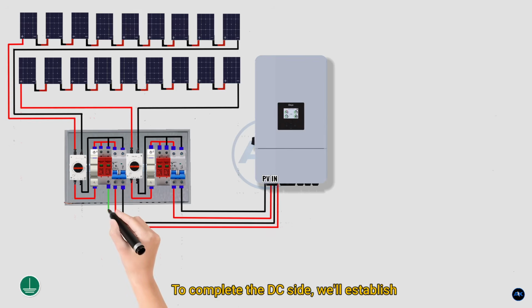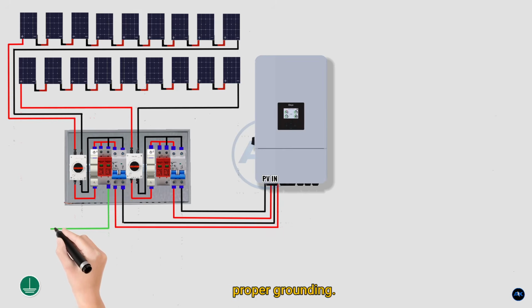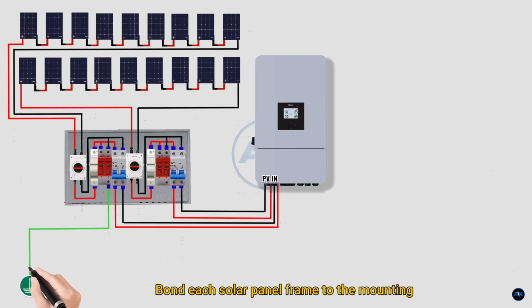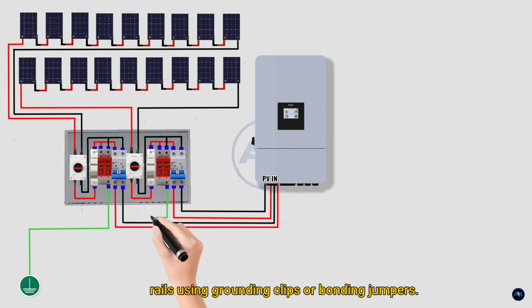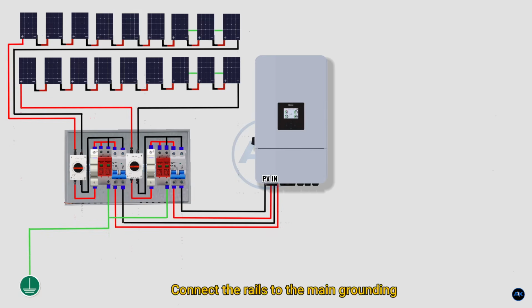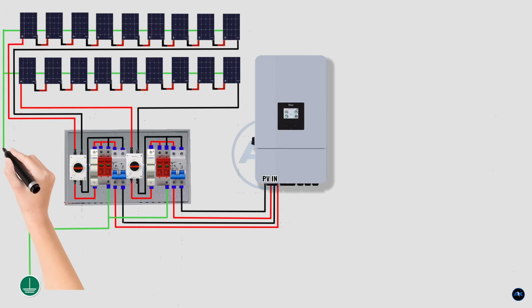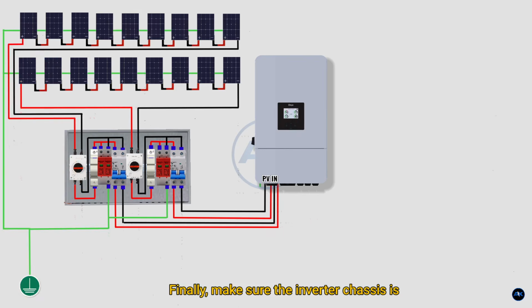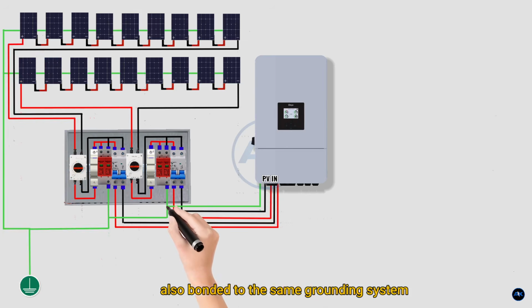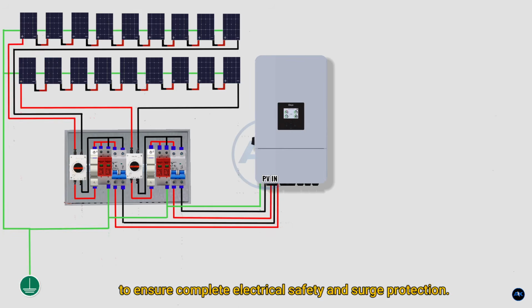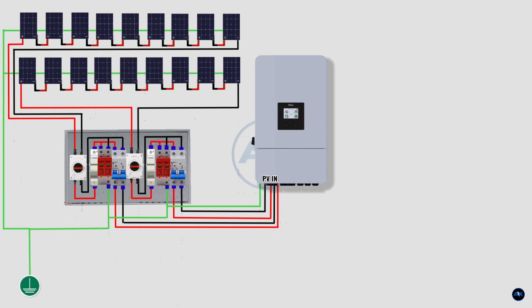To complete the DC side, we'll establish proper grounding. Bond each solar panel frame to the mounting rails using grounding clips or bonding jumpers. Connect the rails to the main grounding conductor, which is tied to the ground rod. Finally, make sure the inverter chassis is also bonded to the same grounding system to ensure complete electrical safety and surge protection. At this stage, our solar array is fully installed, wired, protected, and grounded.